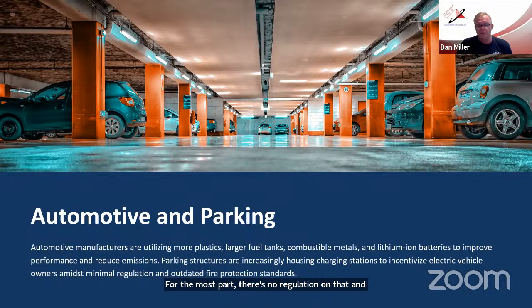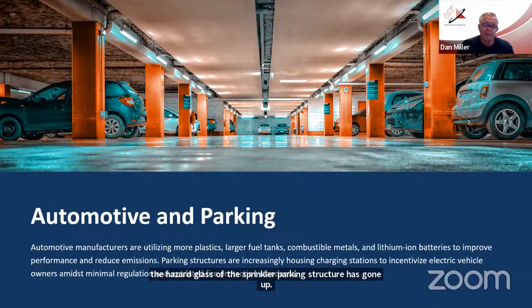So we're looking at a situation where the NFPA, as well as Factory Mutual, have changed their standards and rules so that every parking structure now needs sprinkler protection, and the hazard class of the parking structure has gone up, requiring a higher sprinkler density.